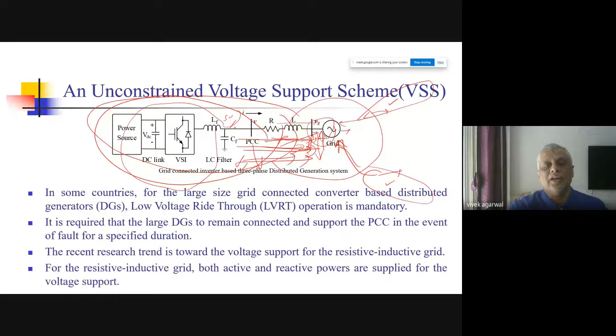So they say don't disconnect immediately. For a few seconds, try to pump suitable reactive power into the system so that this voltage can come up. So if there is no fault, this will come up after some time. But if there is a fault, it will continue to be low, and then you can disconnect. So this is the very important aspect of LVRT.